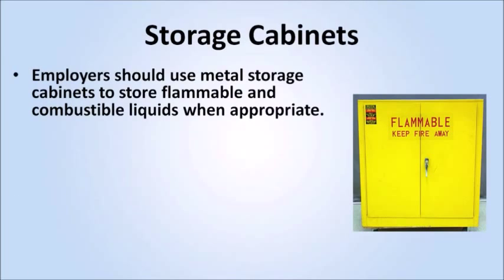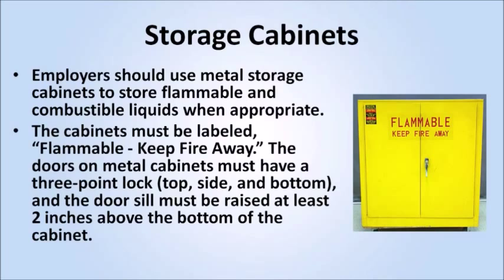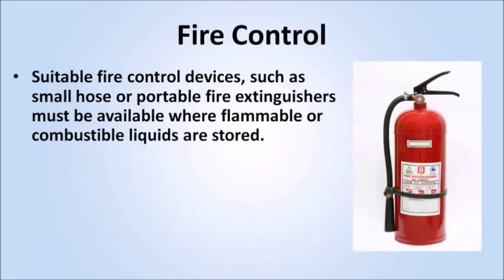Employers should use metal storage cabinets to store flammable and combustible liquids when appropriate. The cabinets must be labeled 'Flammable — Keep Fire Away.' The doors on metal cabinets must have a three-point lock — top, side, and bottom — and the door sill must be raised at least 2 inches above the bottom of the cabinet. Suitable fire control devices, such as small hose or portable fire extinguishers, must be available where flammable or combustible liquids are stored.